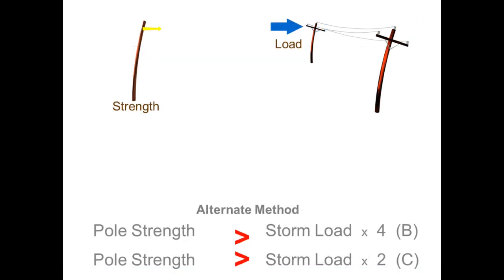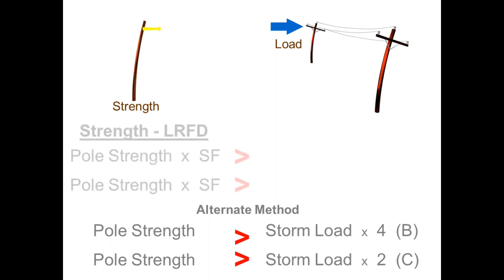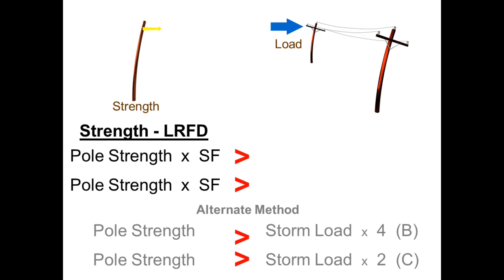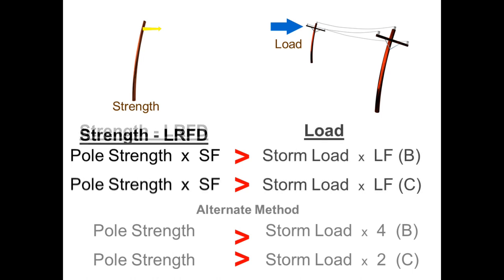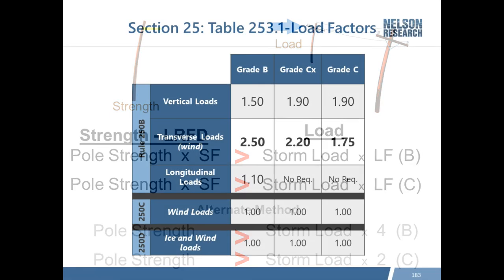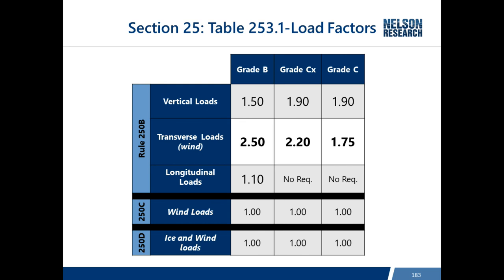Combining strength and load: in previous editions of the NESC, required pole strength was determined by multiplying storm load by an overload capacity factor — 4 for Grade B and 2 for Grade C. Today's NESC uses the LRFD format: pole strength times a strength factor must be greater than the storm load times a load factor. Table 253.1 provides load factors for wood poles, ranging from 2.5 down to 1.75 for different grades.